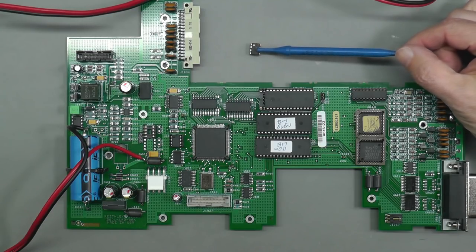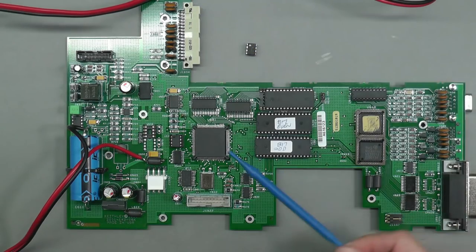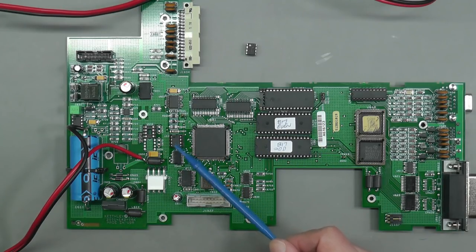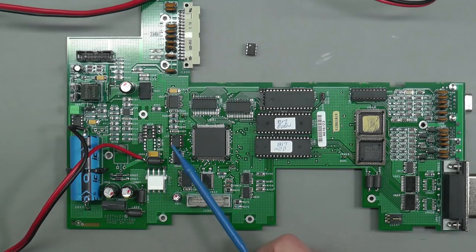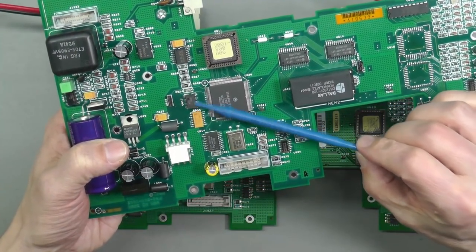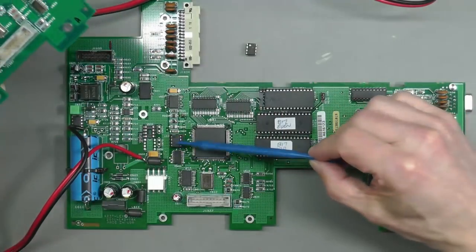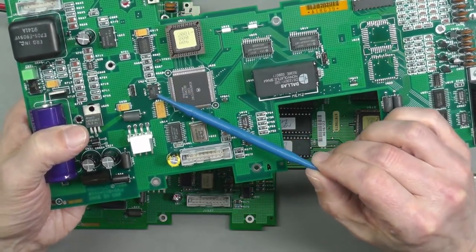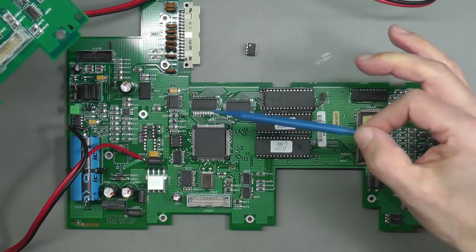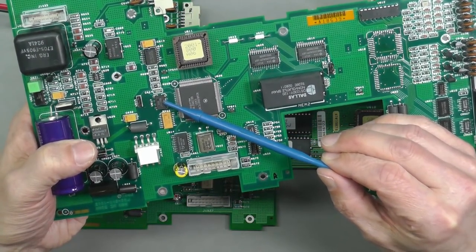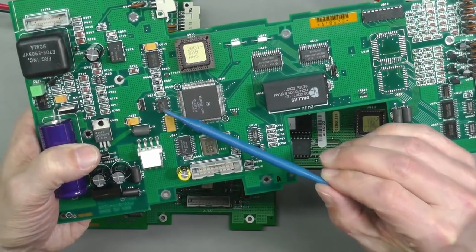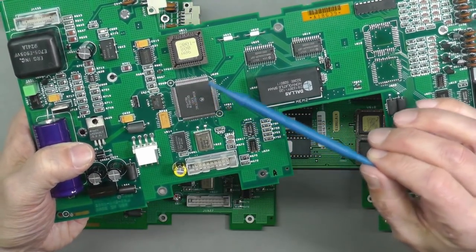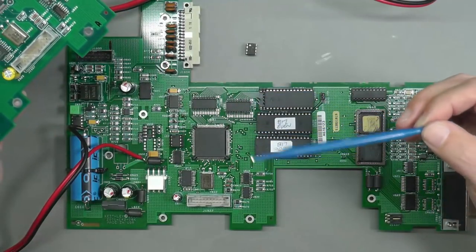I've gone and fitted a brand new blank one and I have powered up and everything's just the same. Calibration lost, not a surprise, the EEPROM's empty. Now I could go and pull the chip from this board and read the contents out on it and program that blank. So I think I will go ahead and do that. There'd be no harm in doing that. The calibration data in here won't be valid of course for this board, it's a completely different analog board that we're going to be using. But at least we'll have some data of some sort in there, assuming the layout of that data is the same for this digital board.